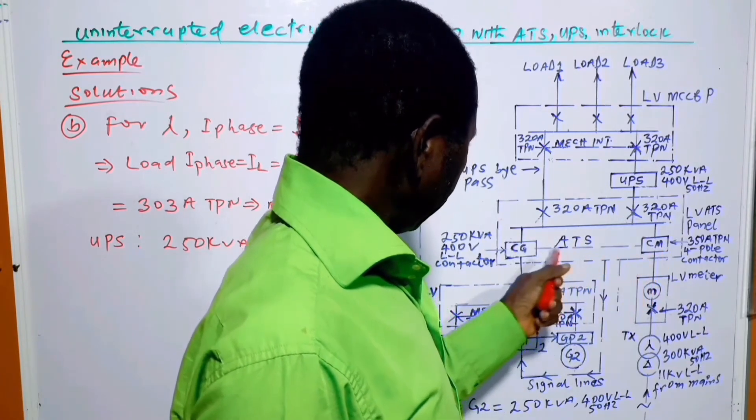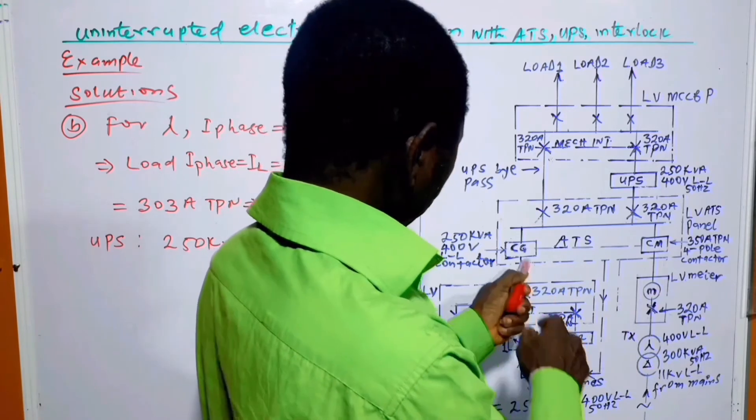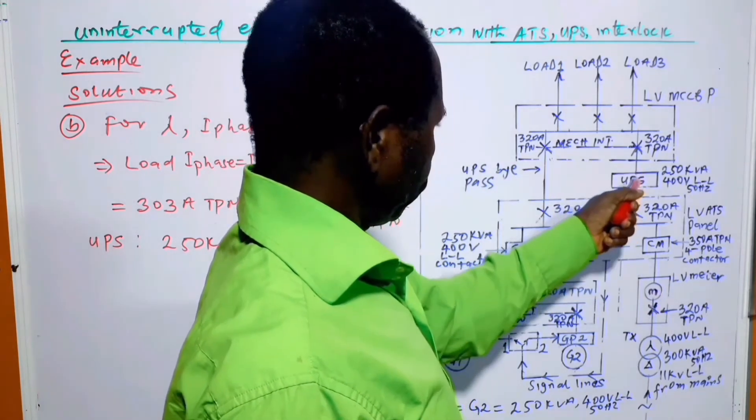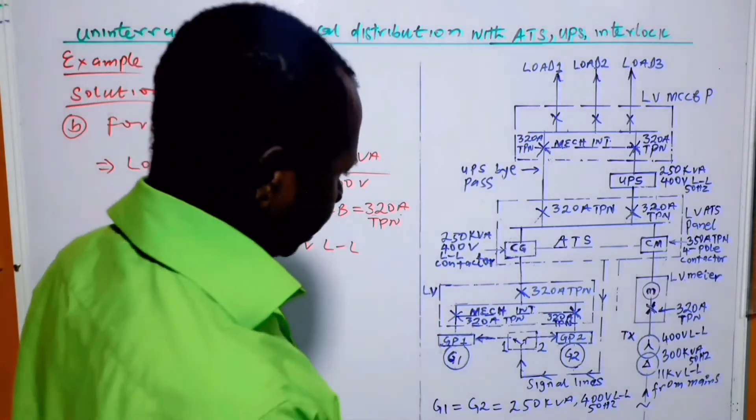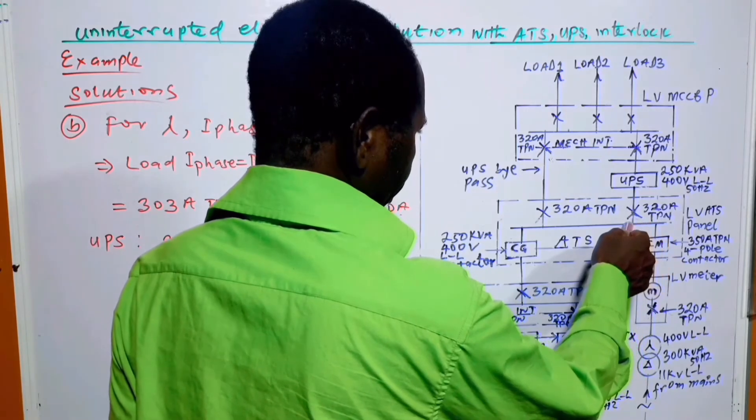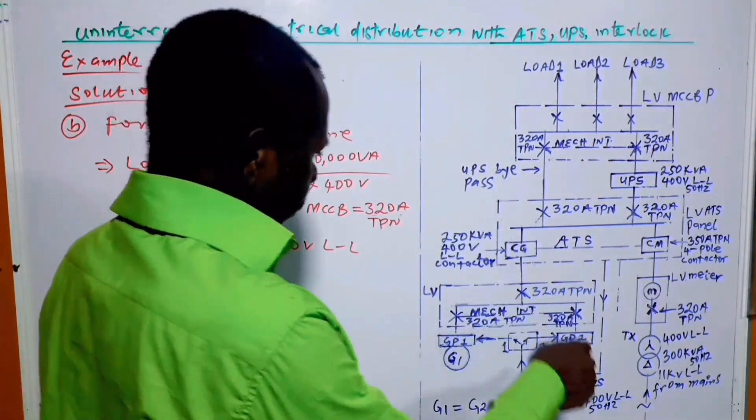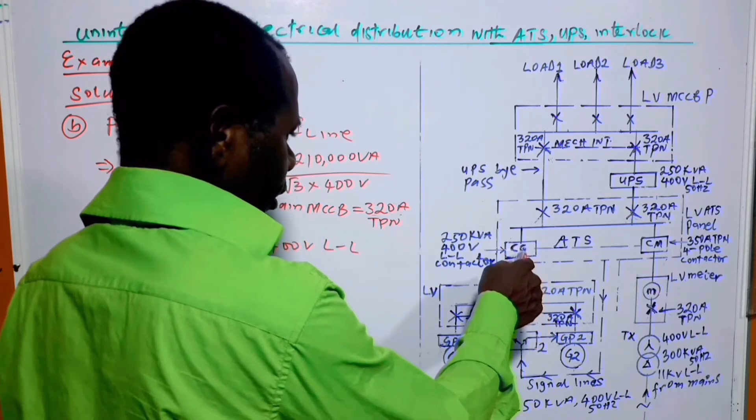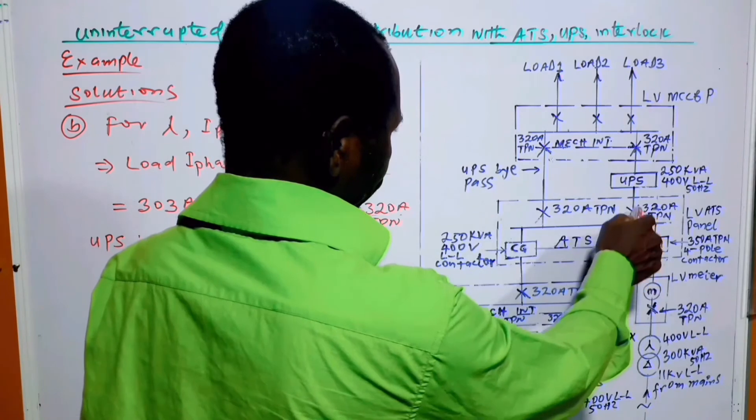From here, if the mains has failure, the generator output continues to be here. From here, it will come and enter the UPS. From the UPS to the load panel. Actually, the flow of power for the two sides is like this. From here, through the meter, that is the mains, through this contactor, through this bus section, to the UPS, to this circuit breaker, and to this load bus section. Even for the generator also, the output of the generator comes here, it goes into the contactor for the generator, and the power is delivered to this common bus section. From here, it goes through the UPS as well.